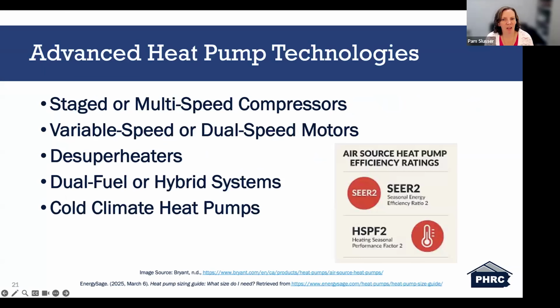Some advanced heat pump technologies have been introduced over the years, making heat pumps more and more energy efficient. And I'm sure as time goes on, there's going to be more as we move down the road too. So the first one there, the staged or multi-speed compressors, they let heat pumps operate close to the heating or cooling capacity needed at any outdoor temperature. They save energy by reducing on or off operation and compressor wear. Their inverter-driven systems can modulate their speed capacity at near infinite degrees, between low and high settings, running more efficiently and maintaining consistent comfort.